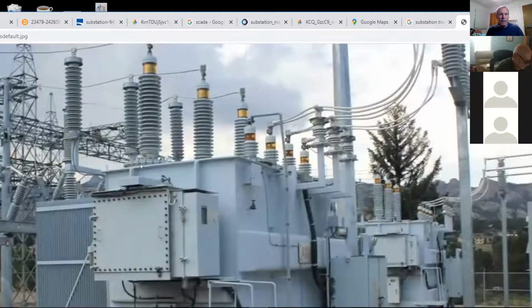Although it can't be seen, the CT and the PT transformer for converting amperage down to a readable level and voltage down to a readable level are encased in the transformer. So they're not showing like the rings that you had on the breaker. So I have a CT on this side and a CT on this side and a PT on this side and a PT on this side inside the tank of the transformer. What does a CT stand for?